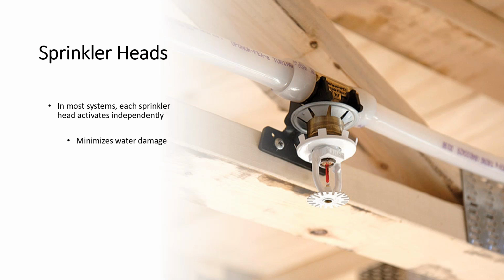Okay, let's move on to the second component of interest today, which is the sprinkler heads. In most systems, each sprinkler head activates independently of each other, and it is triggered only when the temperature reaches a specific level, which helps minimize water damage from the discharge from that sprinkler head. What you see in some movies, that when one sprinkler head is activated all of them go off, is just not very accurate. There are some sprinkler systems that do that. However, not all of them activate like that.